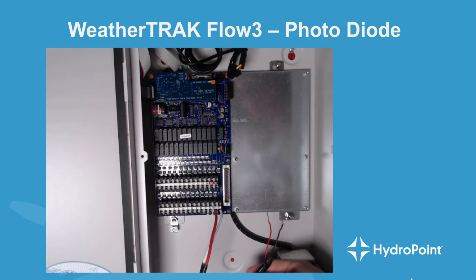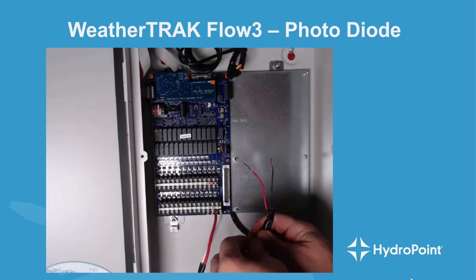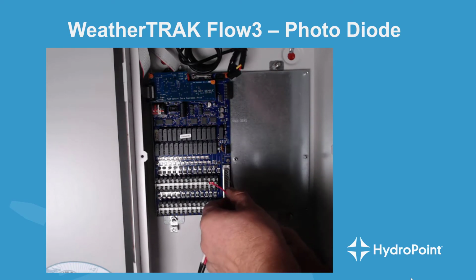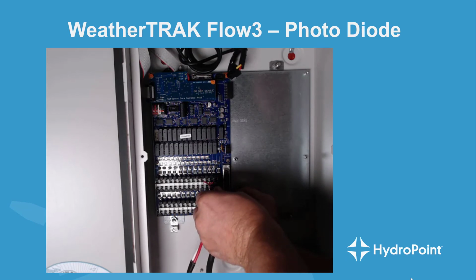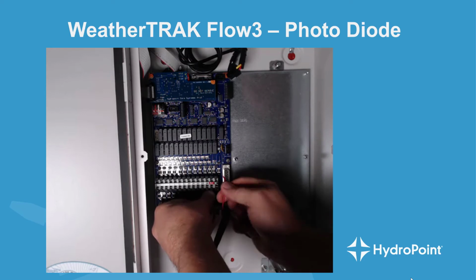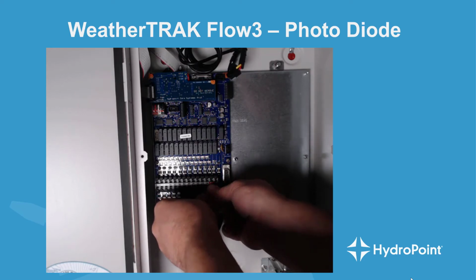Then we'll locate our shielded wire that controls our flow sensor. From this we have a black and a red. The black goes into the VC or valve common that's labeled in black, and then the red goes into the red FL1 port. Black to black, red to red.